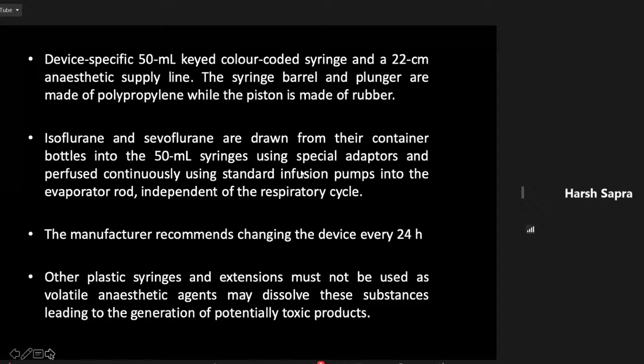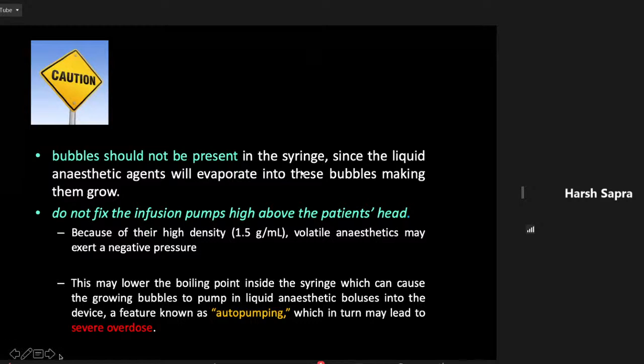So the reason I was telling you that there shouldn't be any bubbles in the syringe is because the liquid anesthetic agent will evaporate into the bubbles, making them grow. And do not fix the pump high above the patient's head. The reason is this may lower the boiling point inside the syringe and can cause the growing bubble to pump the liquid anesthetic bolus into the device, a feature called auto pumping if the bubble increases. So make sure that the pump is lower than the head level, and secondly, that there aren't any bubbles in the syringe.